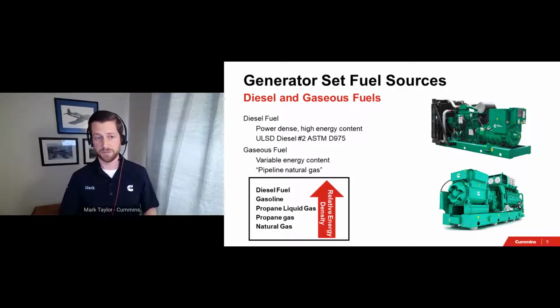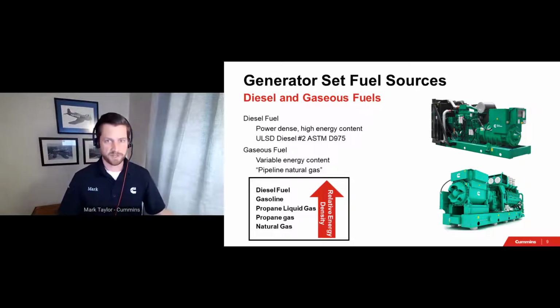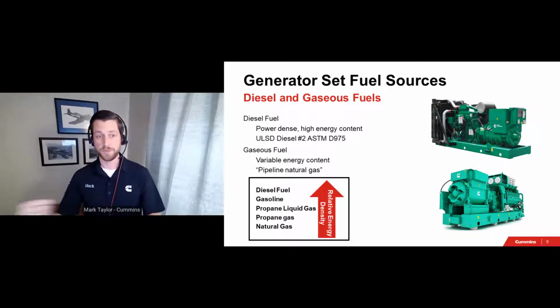At a very high level, this hierarchy I have here shows the relative energy density of the fuels between liquid and gaseous fuels. For the space that they take up, diesel fuel has the highest energy density among these fuels. Historically, it has been perhaps too easy to draw a correlation between energy density and generator set performance, such as starting times and transient performance when taking on heavy loads, for example. But the advances in technology have been trending in a way that blurs the lines between these two notions. We'll get back to that point as we go through the performance requirements section of this presentation.